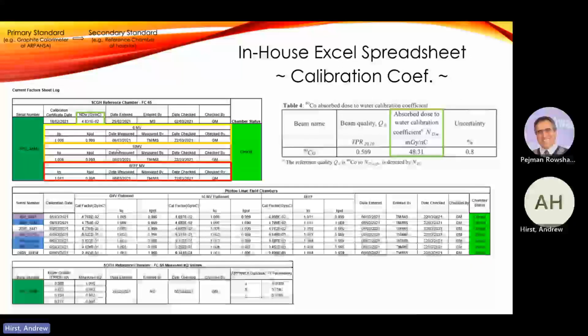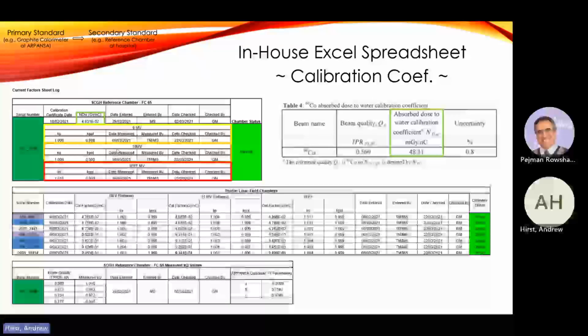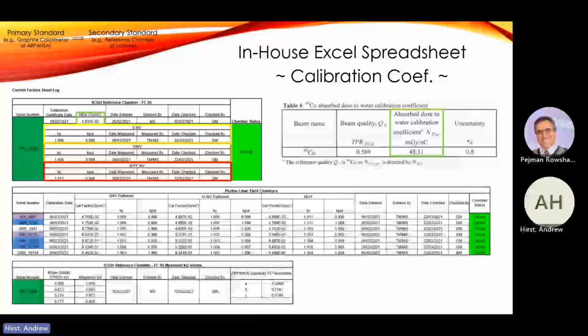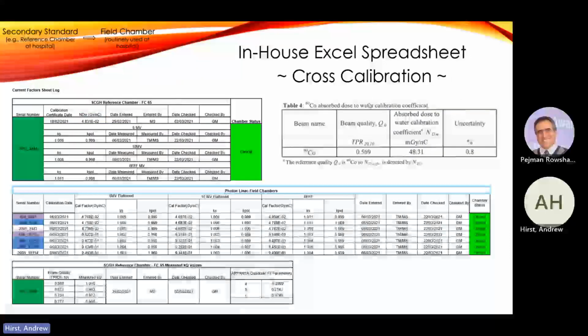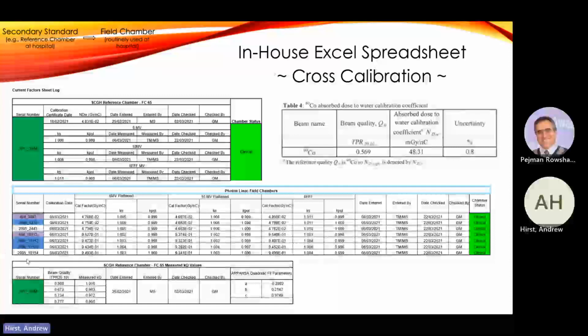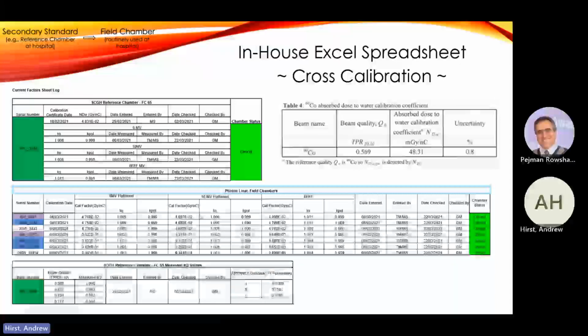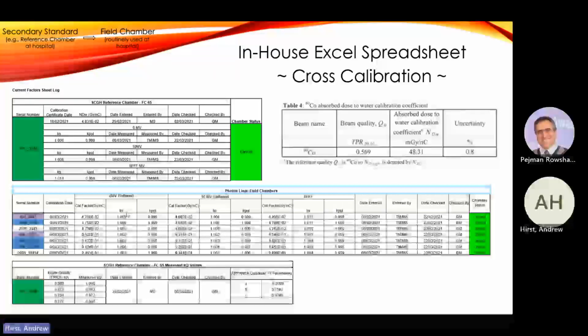And for each energy, we'll measure the recombination and polarity corrections, and then cross-calibration. So this was our reference chamber, and as I said before, we need to transfer that to all of our field chambers. These are the chambers here on the left. You can see for 6 MV, 10, 6 FFF, we have our cross-calibration factor, as well as our corrections for recombination, polarity.